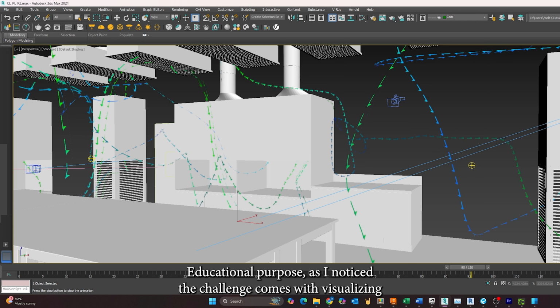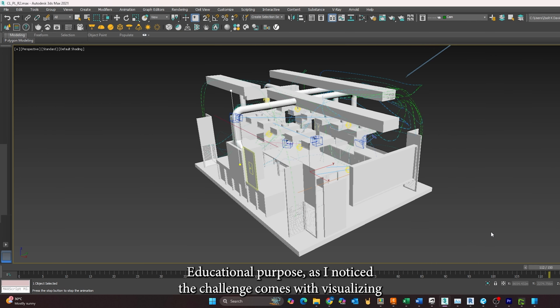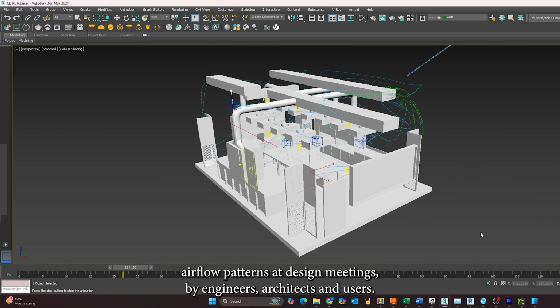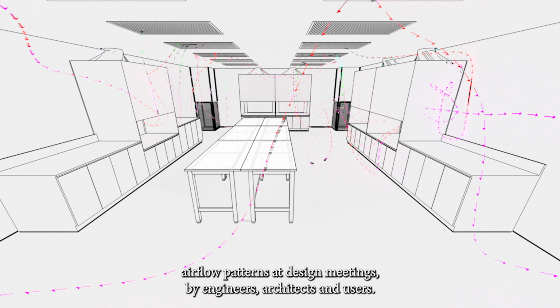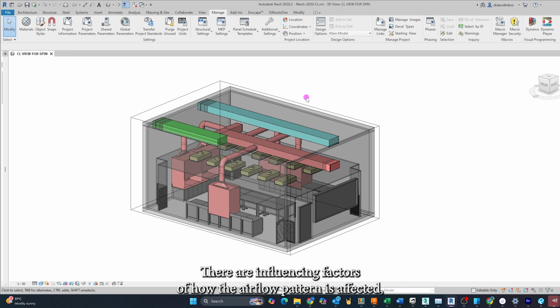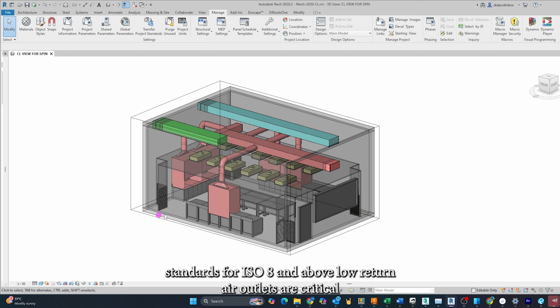Educational purpose. I noticed the challenge comes with visualizing airflow patterns at design meetings by engineers, architects and users. There are influencing factors of how the airflow pattern is affected by furniture arrangement, laboratory equipment placement, exhaust requirements, air intake and outlet locations. Example: in a GMP cleanroom standards for ISO 8 and above, low return air outlets are critical to vent out the room and meet particle count requirements.